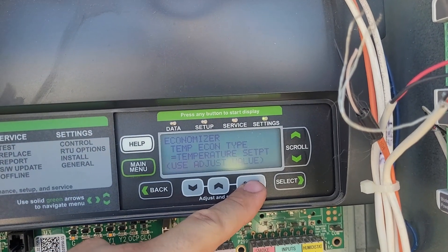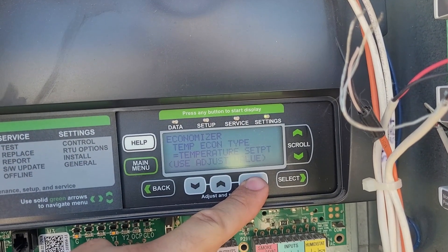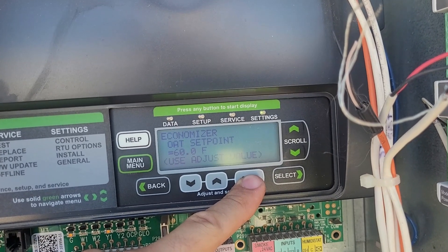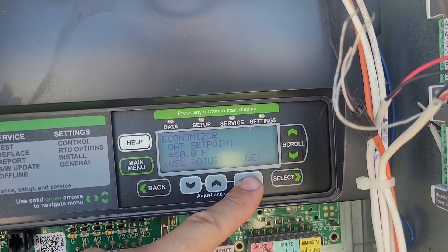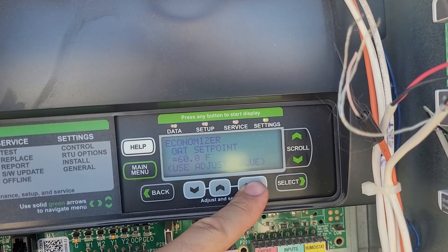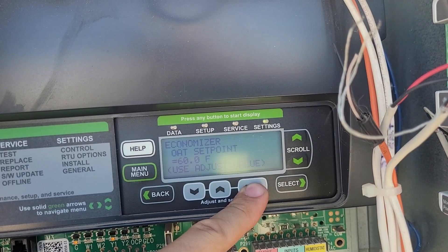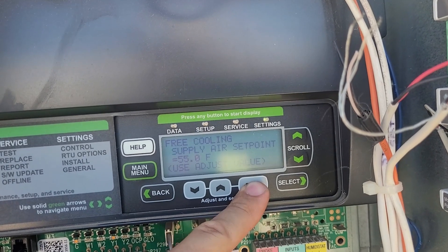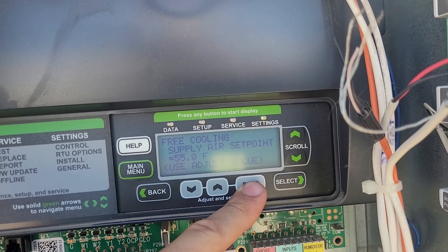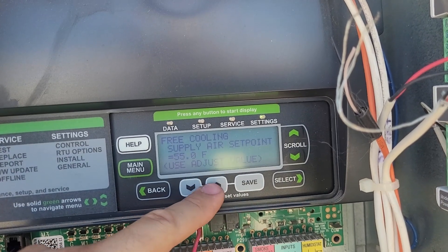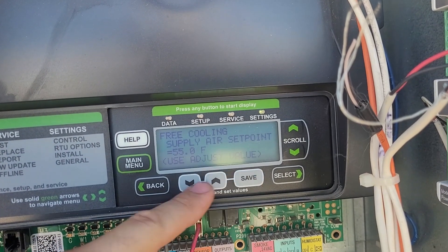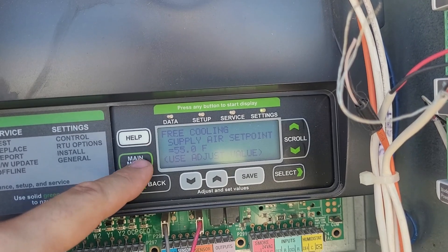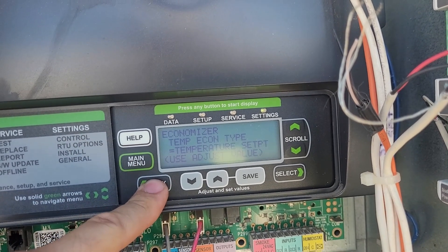Temperature set point looks good, so we're going to move on. The outside air temperature set point should be 60 degrees — or 55 degrees if you're in a very humid area — and then the supply temperature should always be 55 degrees. You can adjust it here and then press Save. This one's done.